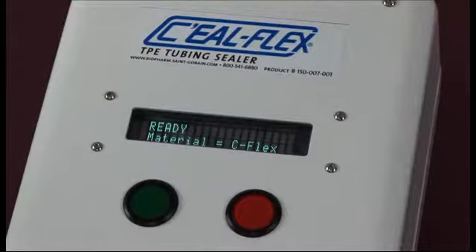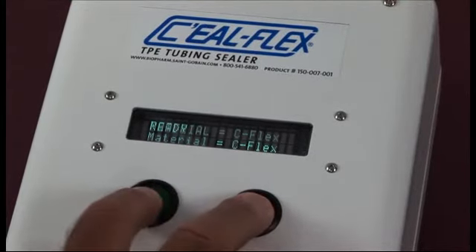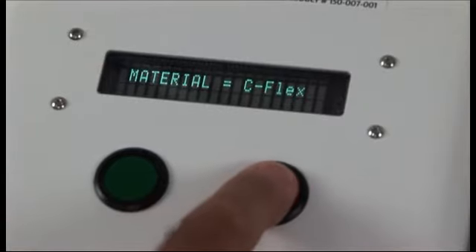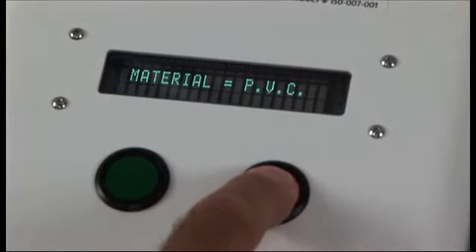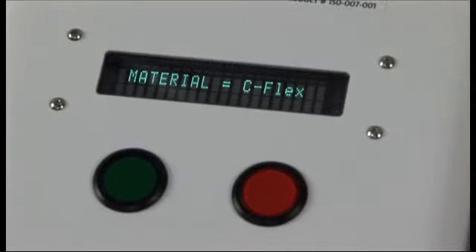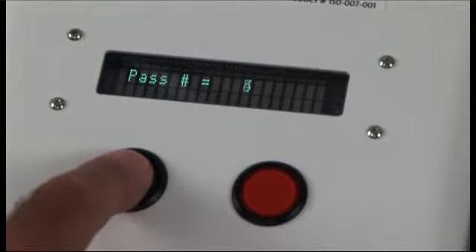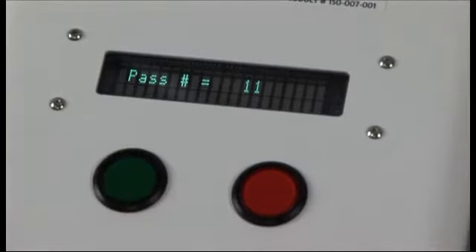To access the settings, use the preset password. Press the red button followed by the green button, and it will show you the material it's currently set for. Then you can cycle it through and change settings to use other materials besides C-Flex. You'll see it cycle through the settings at timed intervals. Adjustments up and down can be made when the reading is on the screen.